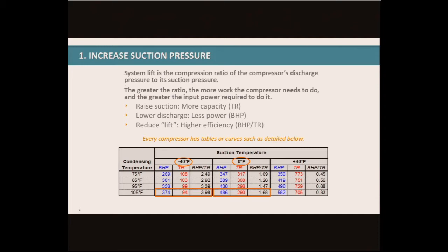If we're able to increase that suction pressure — and this is an extreme example going from a minus 40 to a zero degree suction, but the idea holds true incrementally — in this situation, from minus 40 to zero, our brake horsepower goes from 374 to 486. You might think our brake horsepower just went up, but the key is to look at the tons as well. Our tons of refrigeration went from 94 to 290, and our overall efficiency went from 3.98 to 1.68 brake horsepower per ton. So our efficiency vastly improved — we're getting a lot more refrigeration effect out of that compressor for less horsepower.